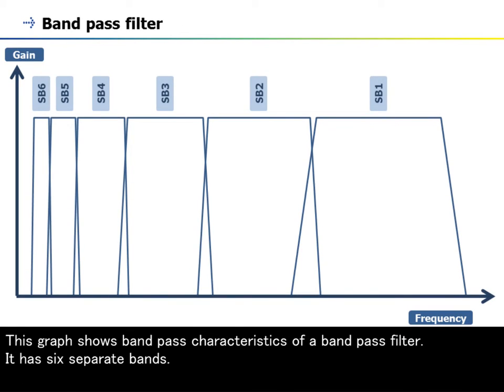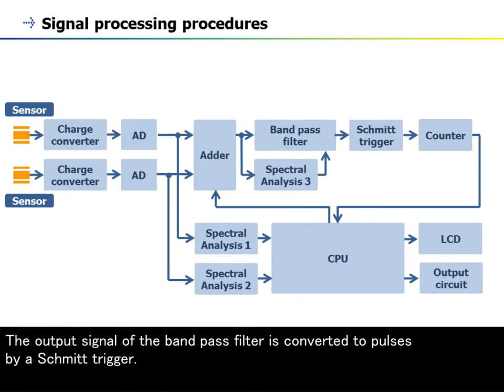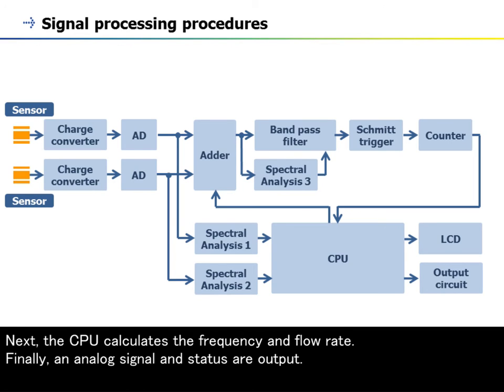This graph shows band-pass characteristics of a band-pass filter. It has six separate bands. The output signal of the band-pass filter is converted to pulses by a Schmitt trigger. Next, the CPU calculates the frequency and flow rate. Finally, an analog signal and status are output.